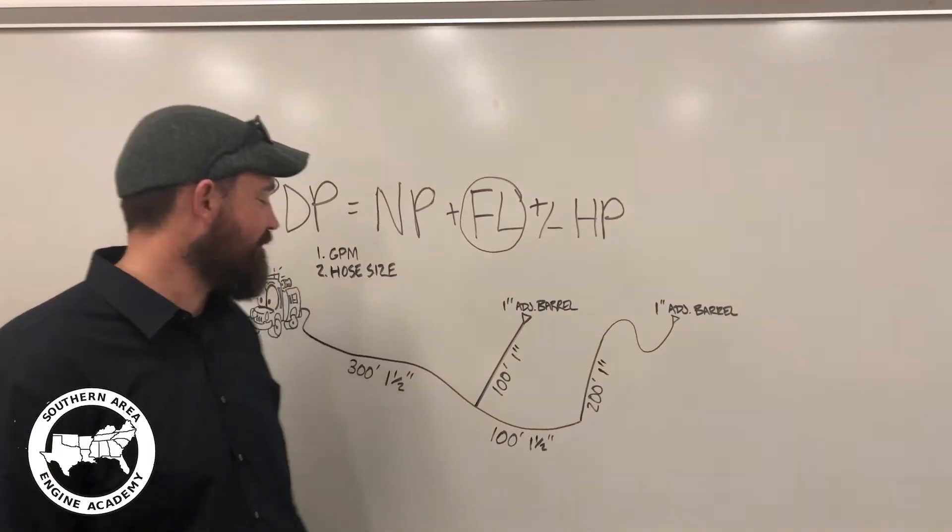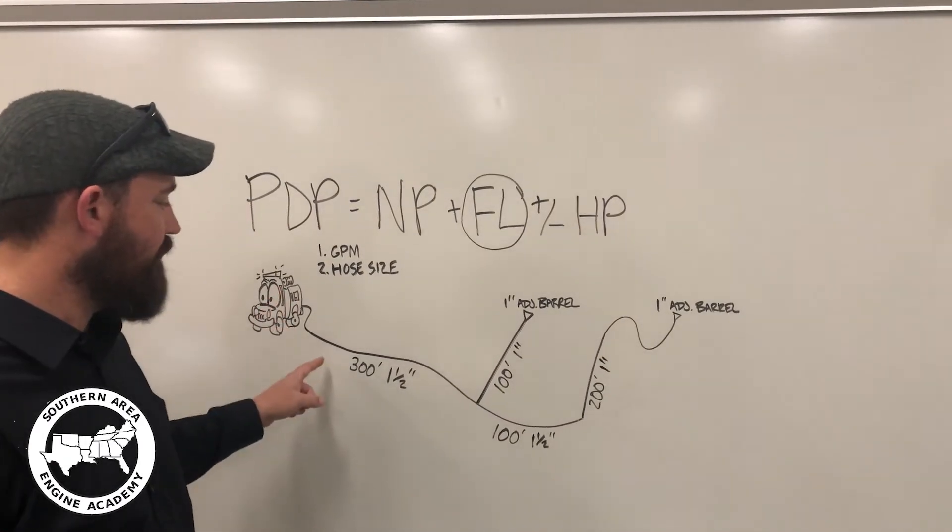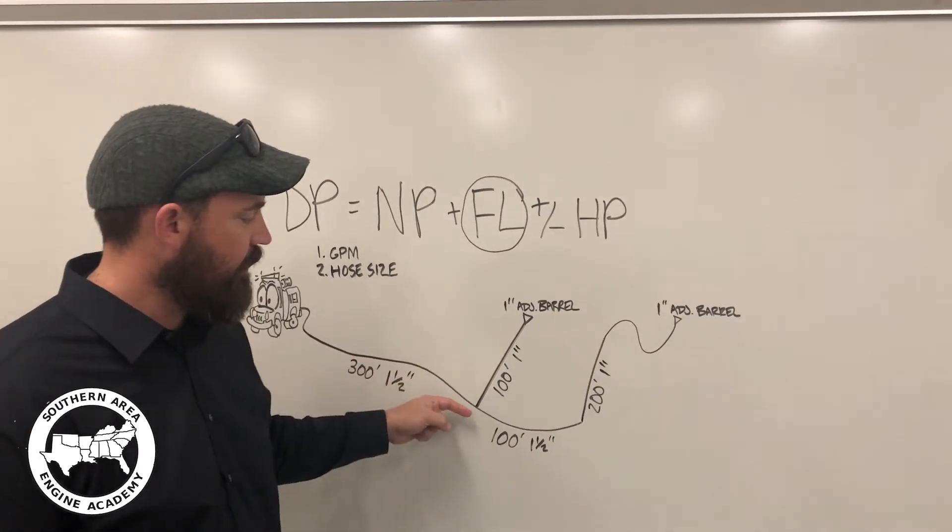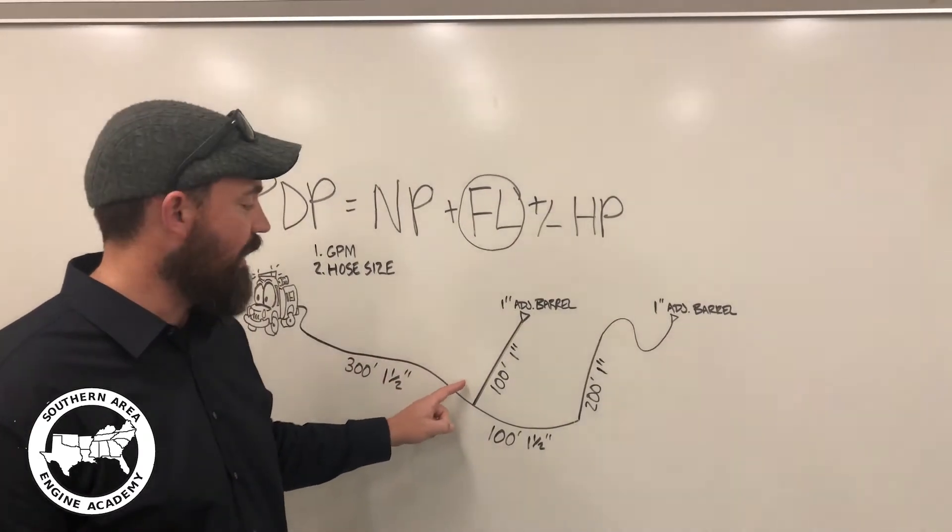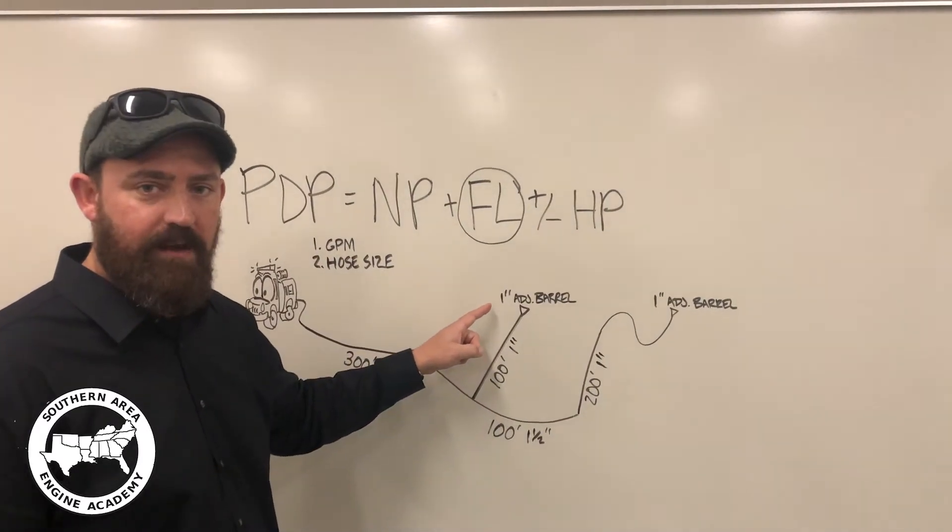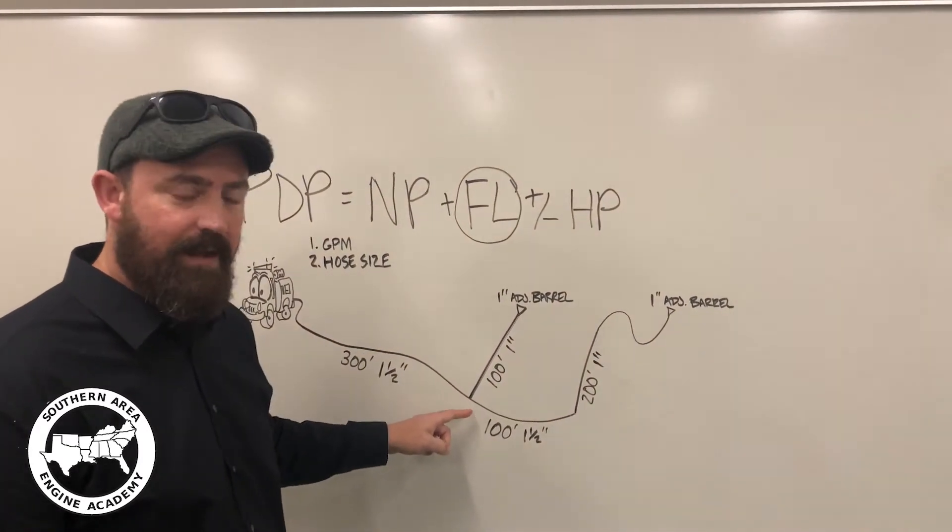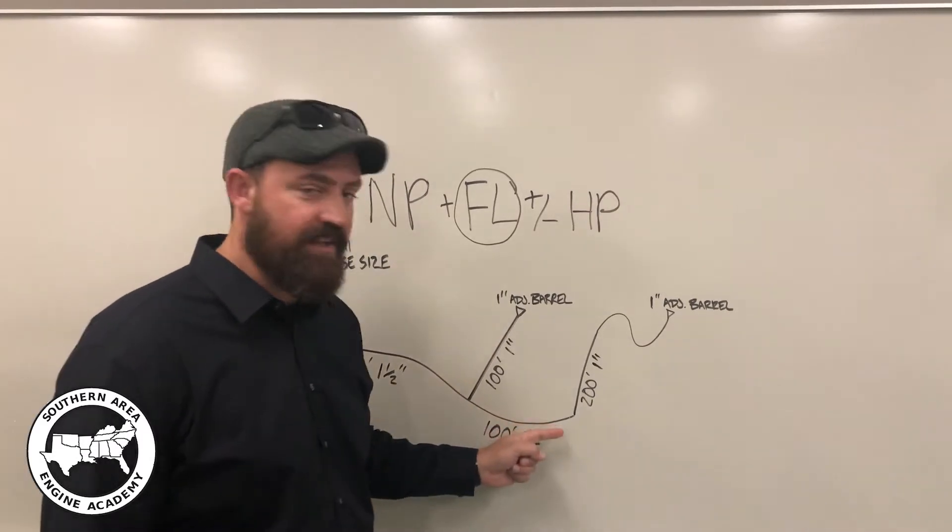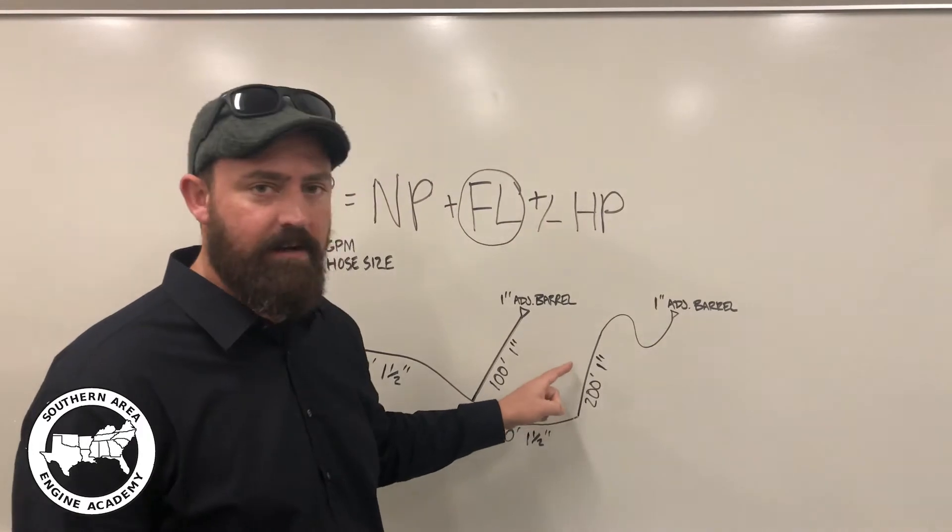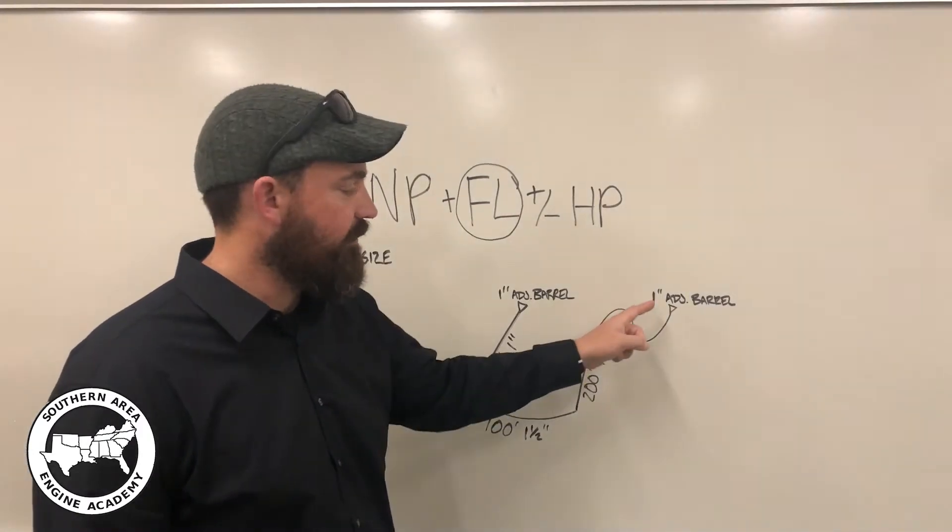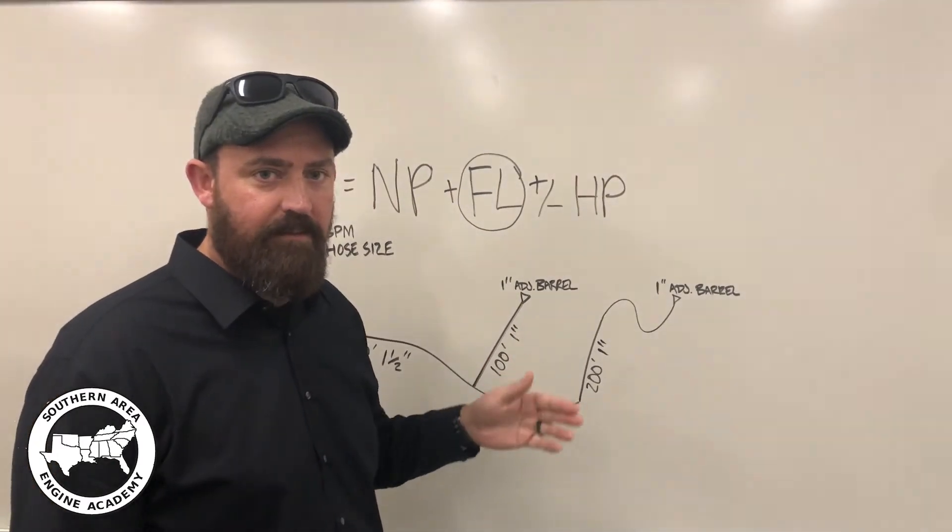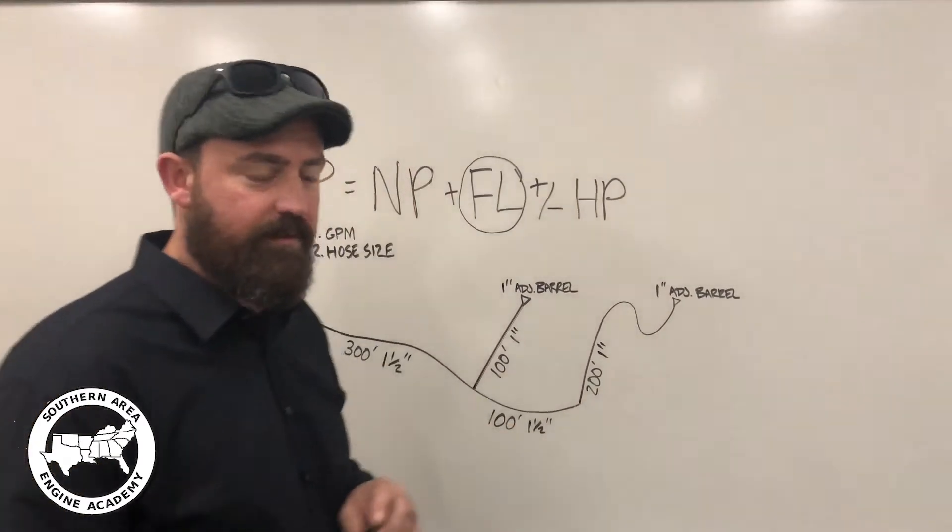So here's our problem. Now, we have 300 feet of inch and a half trunk line going to a lateral of one inch, supplying a one inch adjustable barrel nozzle. Past that, we have another 100 feet of inch and a half trunk that's supplying another lateral that's 200 feet of one inch hose, also with a one inch adjustable barrel. And so I'm just going to work this problem out, get the friction loss, and then we'll go over the rules of thumb later.